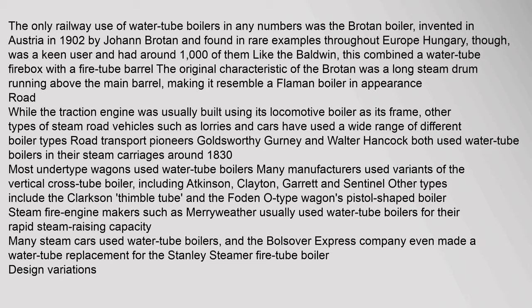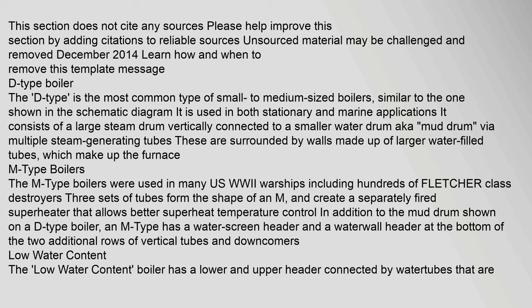The D-type is the most common type of small to medium sized boilers. It is used in both stationary and marine applications. It consists of a large steam drum vertically connected to a smaller water drum, also known as a mud drum, via multiple steam generating tubes. These are surrounded by walls made up of larger water-filled tubes which make up the furnace.